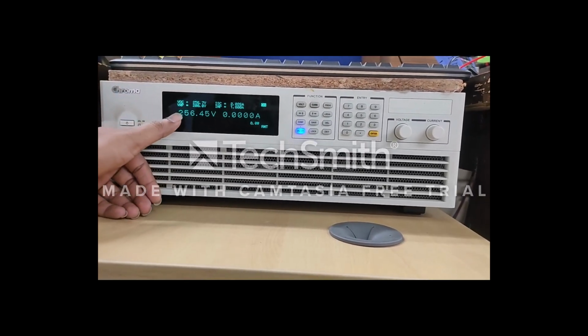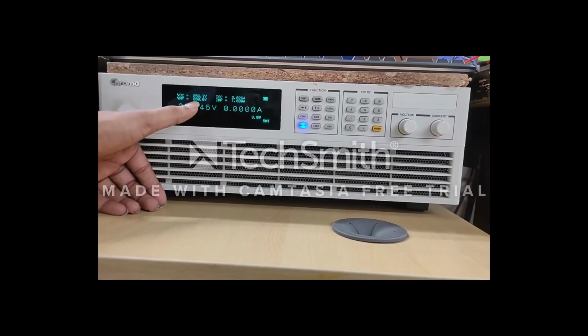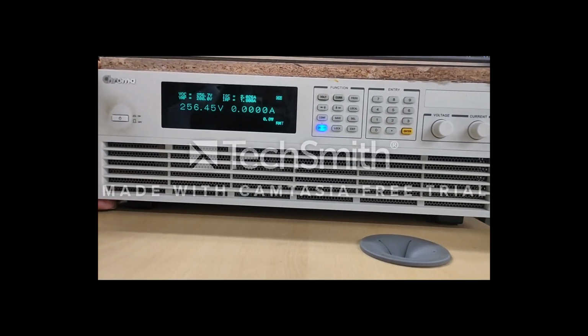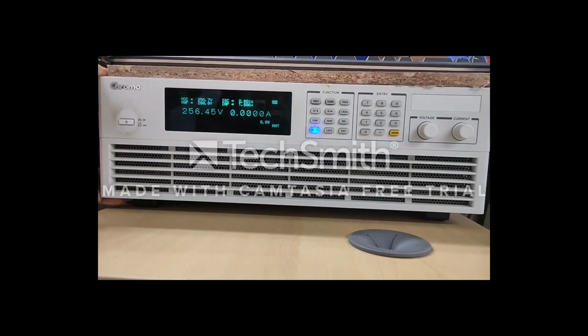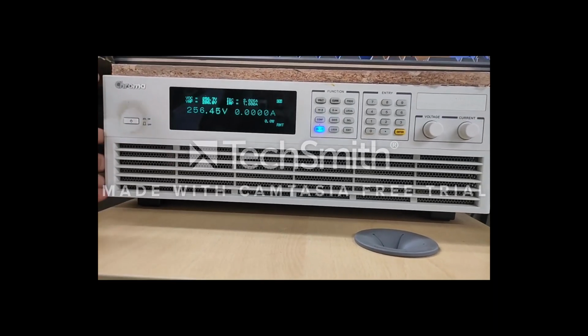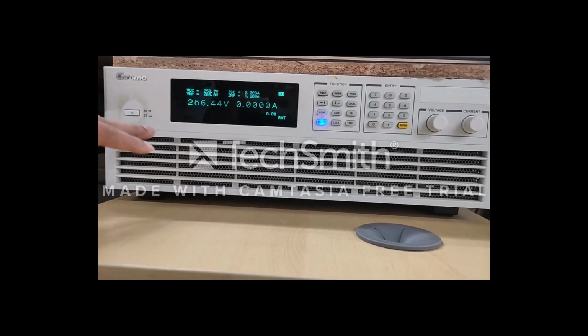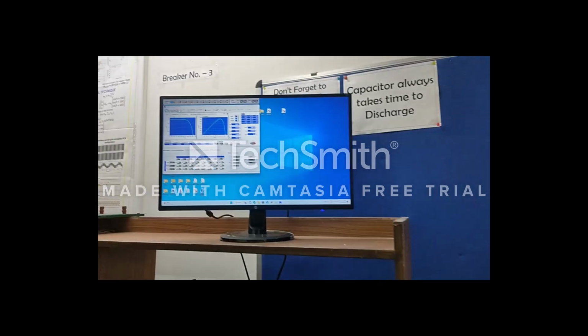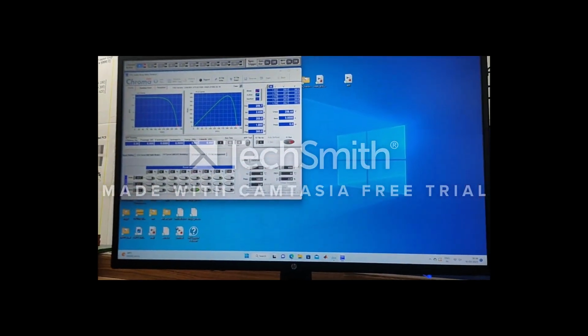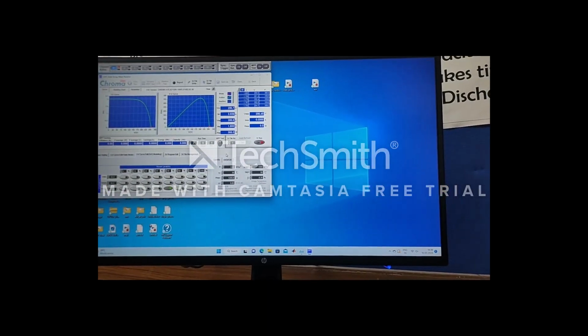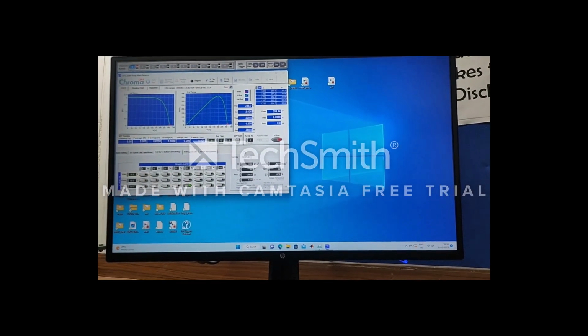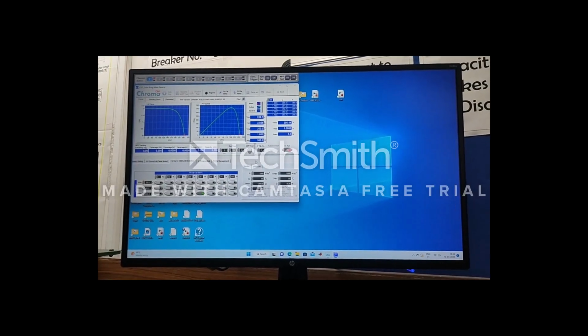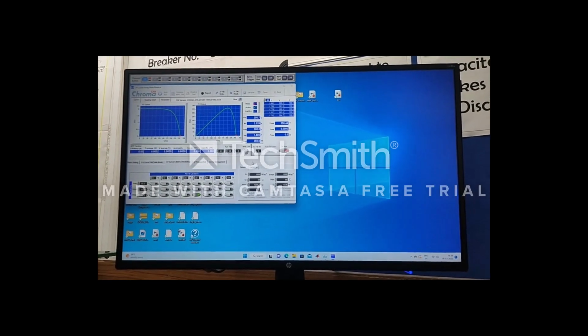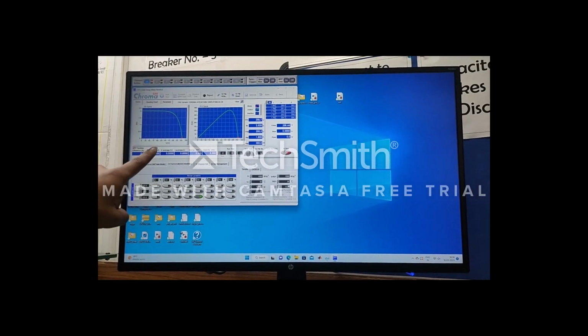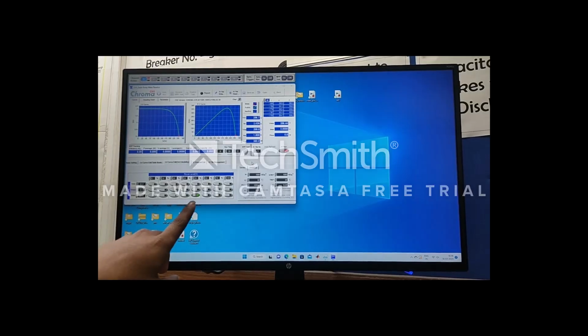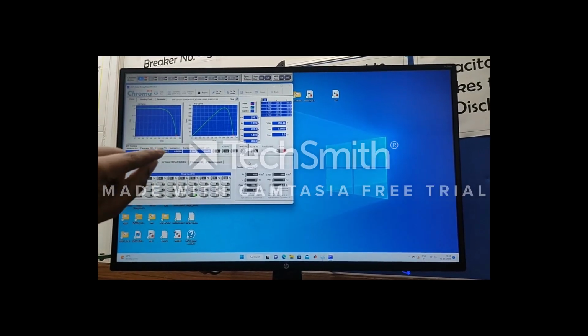We set the open circuit voltage to 256 and VMPP to 200 volt. The solar emulator ratings are 15 kilowatt, 1000 volt, 15 ampere current. It can be operated using the solar emulator software, where we can easily mimic the solar panel characteristics. So that's why we can use the solar emulator anytime, 24 hours. You can see the IV characteristics and PV characteristics. Depending on the irradiance setting, the IV and PV characteristics will vary.